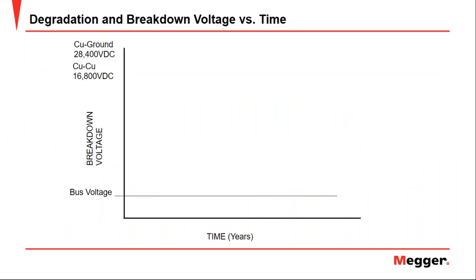Now, let's take a look at the degradation graph. What we can see here is the insulation behavior versus time. It is very important that we clearly understand this graph. Here we can see how the insulation system degrades in an electric motor. No matter how big or small the motor is, no matter its design, its power, or its type, all electric motors show this behavior when their insulation ages.